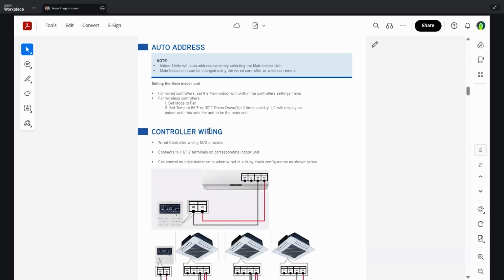You set the mode to fan, set temperature 86 or 30 degrees Celsius, press up and down 3 times quickly. UC will display on the indoor unit. This sets the unit to be the main unit. This applies to wireless controllers.